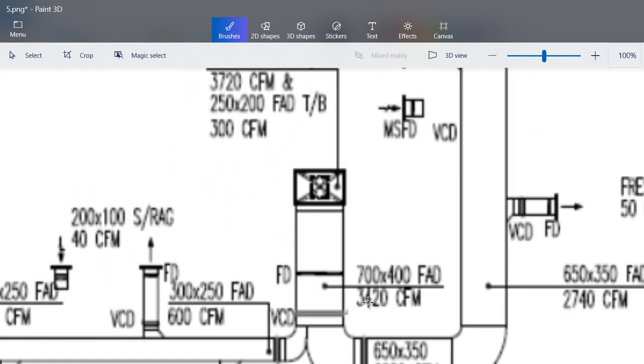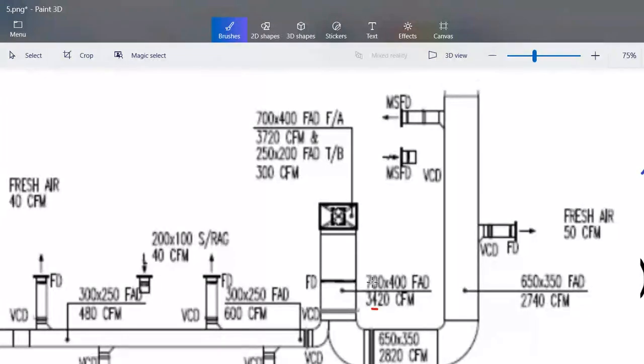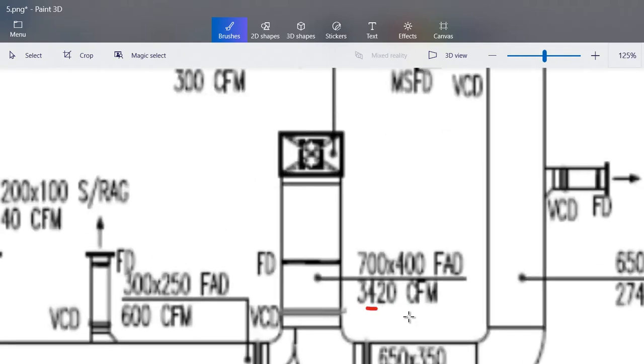We have the duct size of 700 by 400, then the corresponding CFM. Take note of how you annotate the ducting. In your air distribution system, we apply this — so when we annotate, we give a description of your drawing. We have your duct 700 by 400 with the corresponding 3,420 CFM.